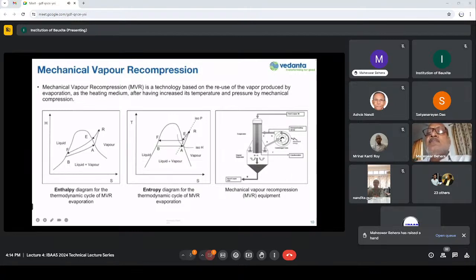The set of recompressors can be one, two or many, depending on the requirement, the temperature and the pressure of the vapor. These compressors are currently electrically powered, and they increase the temperature and pressure of the vapor. Once the energy content matches that of the fresh steam which is initially used, it can be used as a replacement for the fresh steam and reused in the shell. This way, we can reduce the fresh steam requirement, which in turn reduces the fossil fuel consumption.